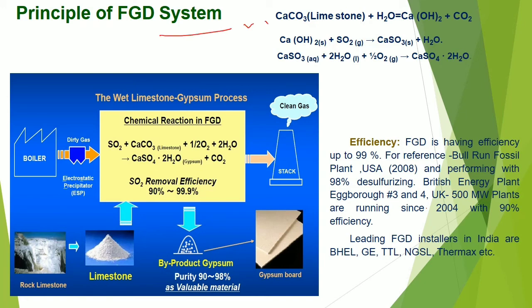The chemical reaction: limestone (calcium carbonate) reacts with water giving calcium hydroxide and carbon dioxide. Calcium hydroxide further traps sulfur dioxide from flue gases making calcium sulfite and water. This calcium sulfite again reacts with water and oxygen giving calcium sulfate 2H₂O, that is gypsum.